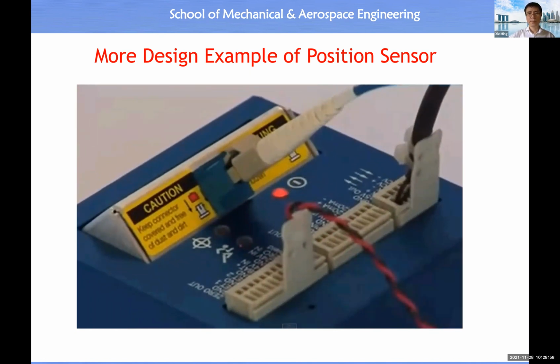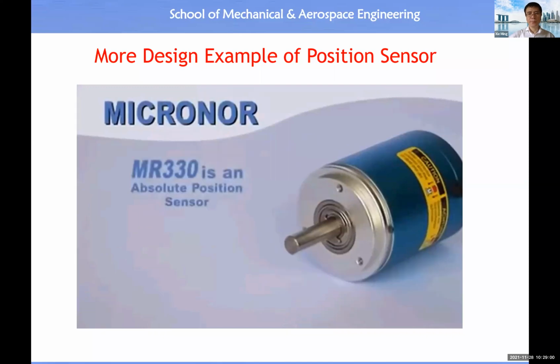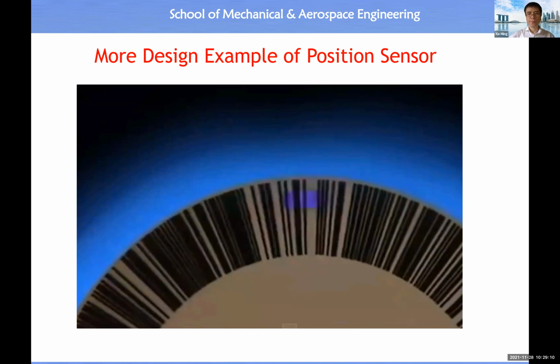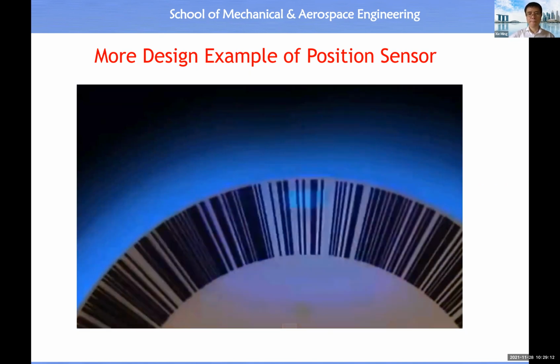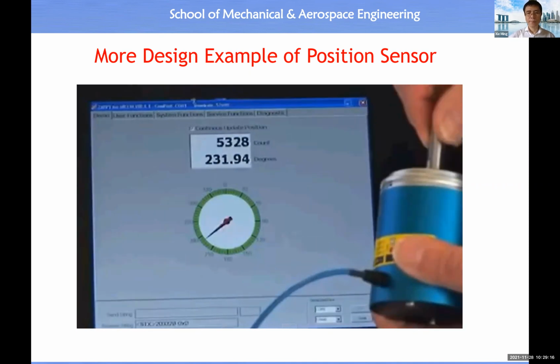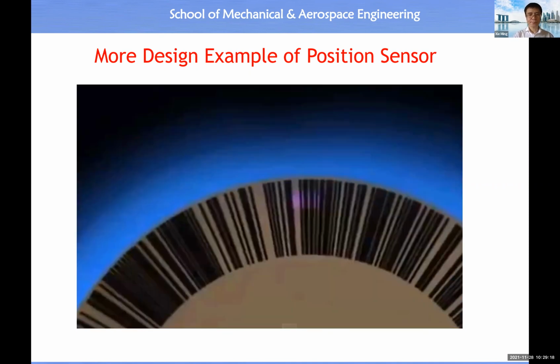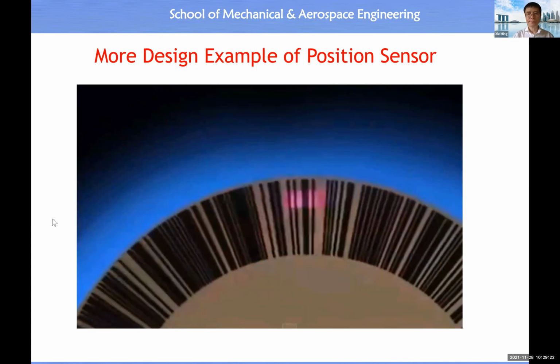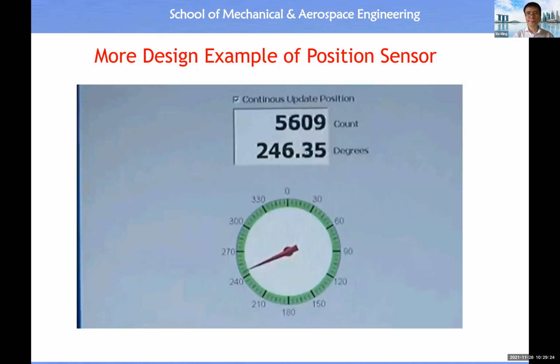The model MR330 is a true absolute position sensor with an incredible resolution of 13 bits. The controller transmits a burst of light to the sensor. Inside the sensor, a code disc modulates the spectral components of the light. The position information is now imprinted in the optical spectrum of the light and guided back to the controller for position readout.